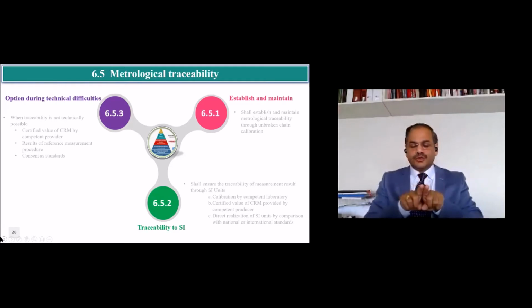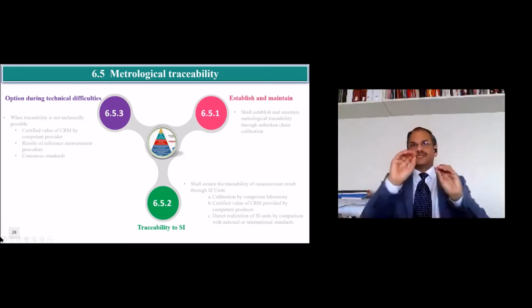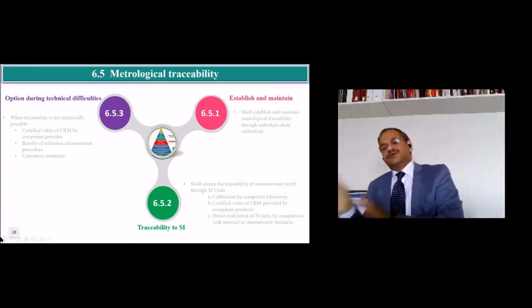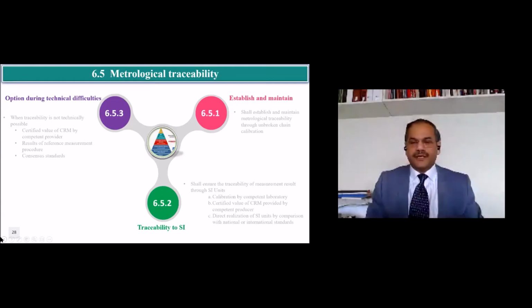So you have to ask him that the calibration certificate he provides has to be accompanied by the traceability certificate, or he has to mention that this instrument is calibrated by this lab, which is an ISO 17025 calibration lab. That is perfectly okay. Okay. Any other question on this?